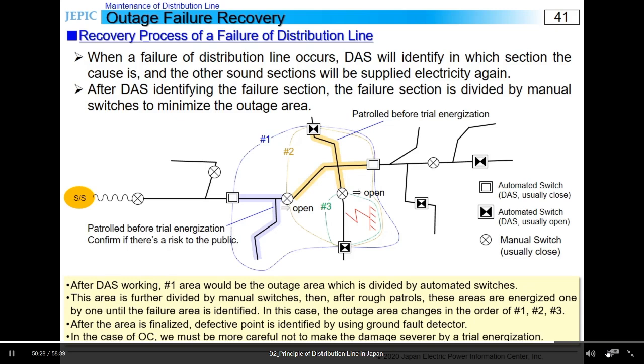So when we do a trial energization to an outage area by a manual switch, we turn it on and off manually and instantaneously within 0.8 seconds. I mean, we turn it on but immediately turn it off again before the CB of the feeder trips. The CB trips in 0.8 seconds if there's a ground fault, but in 0.2 seconds the ground fault current relay works. By monitoring whether that relay works or not, we can confirm if there's a failure in the area where we try to energize. Then, the outage area would be finalized in this procedure.